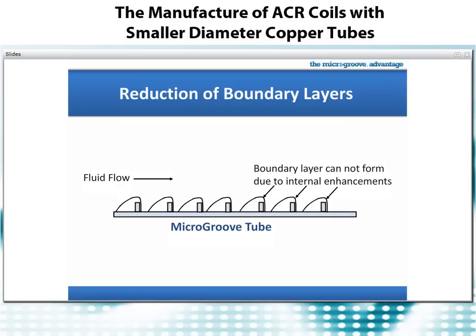Micro-groove tubes have internal enhancements and grooves that reduce the formation of boundary layers. You can see that the boundary layer begins to develop but breaks down as it moves over the grooves. The additional mixing of the refrigerant inside the tube increases the amount of refrigerant that comes in contact with the tube wall. The positive effect on heat transfer from these internal enhancements has been known for a long time and applied commercially for over 20 years. When combined with smaller diameter tubes, we have even more advantages.